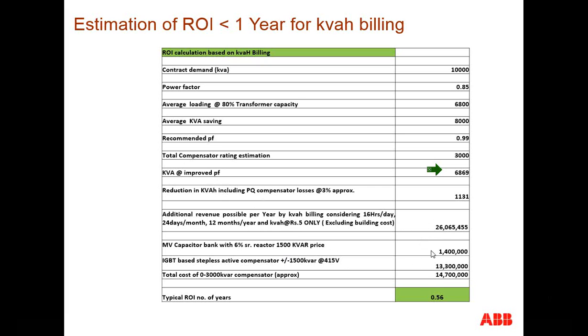If we take an MV solution, it is about, let's say, 1.4 million, and an IGBT based system, even if it's 13.3 million, all put together close to around 15 million. So we get an ROI of less than a year. So this is becoming very attractive. In the process, we are also safeguarding all our equipment.